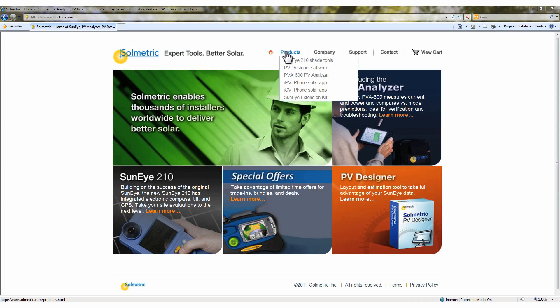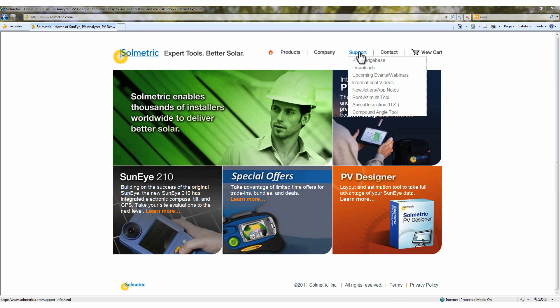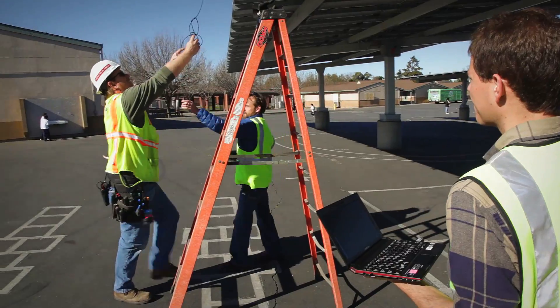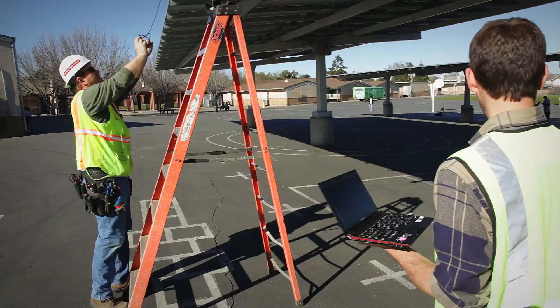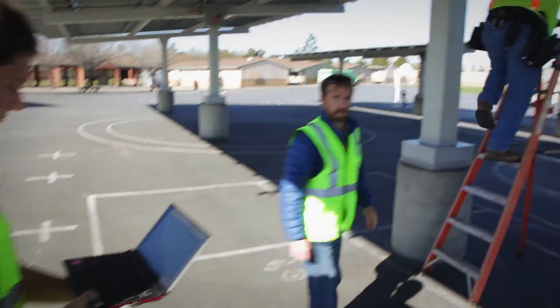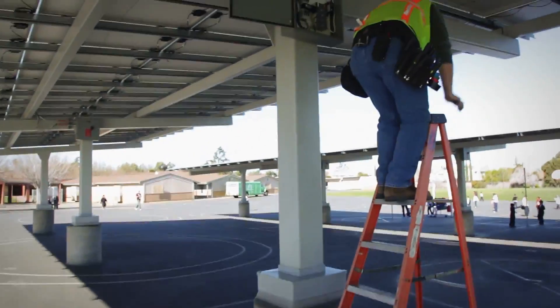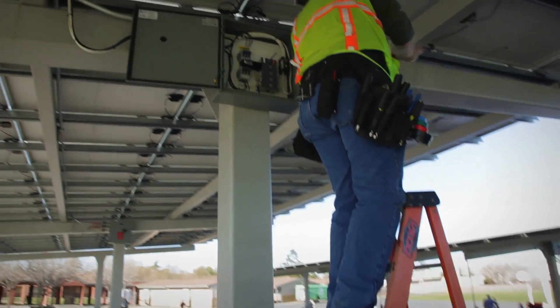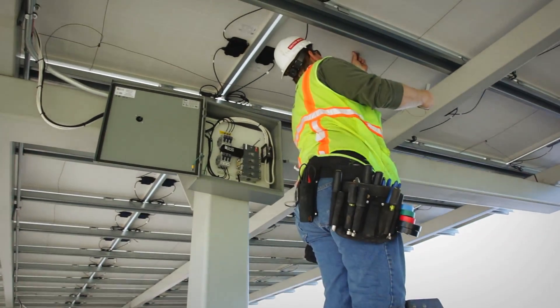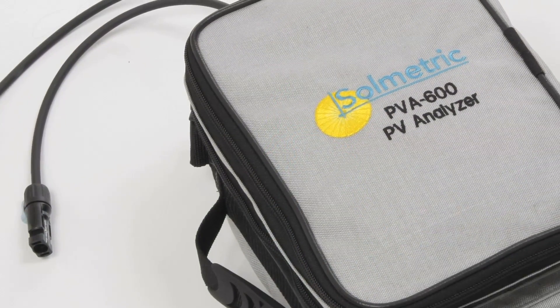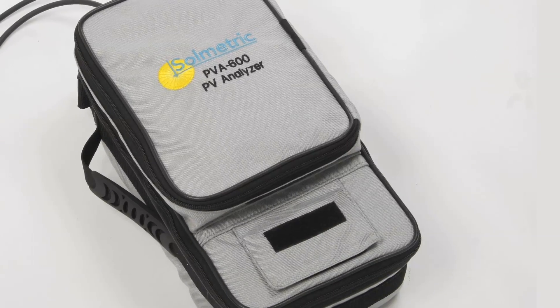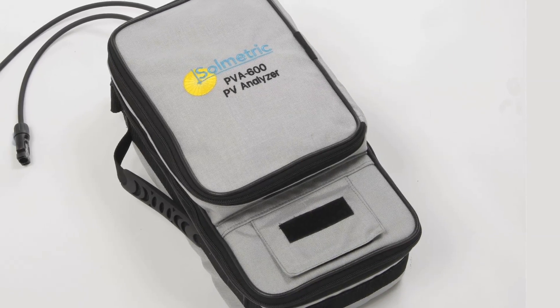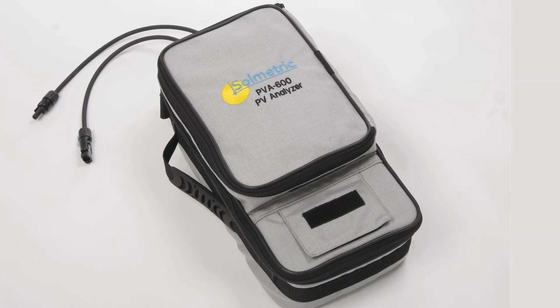A video training series, available from the Solmetric website, provides details on proper operation of the PV Analyzer. PV Analyzer measurements are triggered wirelessly from the PC, allowing the user to move around during operation. This feature also adds a level of safety over handheld solutions in that there are no interconnecting wires to trip over, and the operator does not have to touch anything that is connected to the array. The Solmetric PV Analyzer hardware is also well protected for the operator's safety. The exterior is electrically isolated, and if it senses too much current or voltage during measurement, the PV Analyzer will disable automatically.